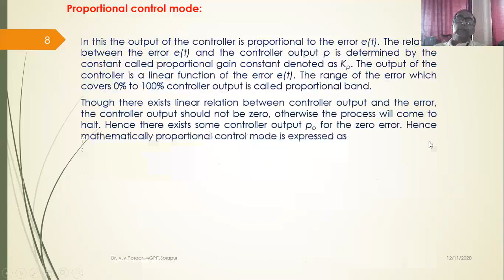This equation we have already seen. If the control variable decreases, causing an increase in the controller output, or an increase in the control variable causes a decrease in the controller output, the action is called reverse action. So the proportional action can be direct action, where with increase in error the controller output is also increasing, and reverse proportional action, where with increase in error the controller output is decreasing. And with decrease in error, controller output is increasing. That is called reverse proportional control action.